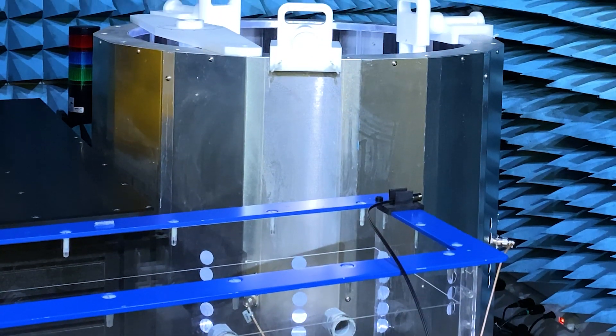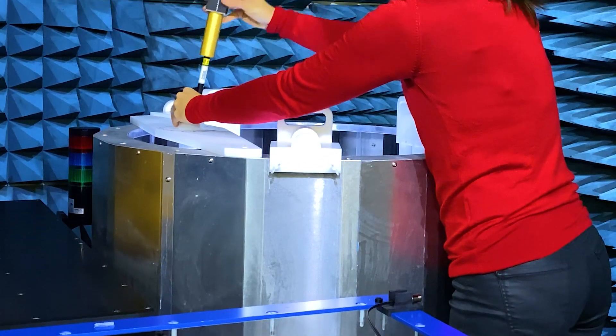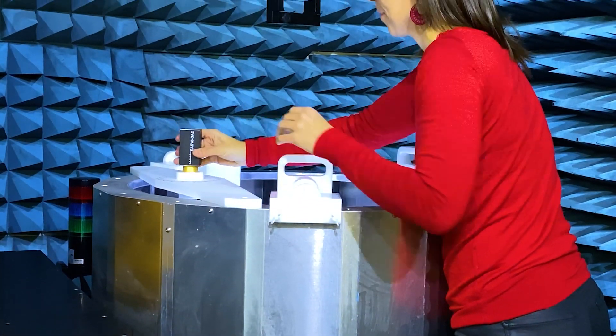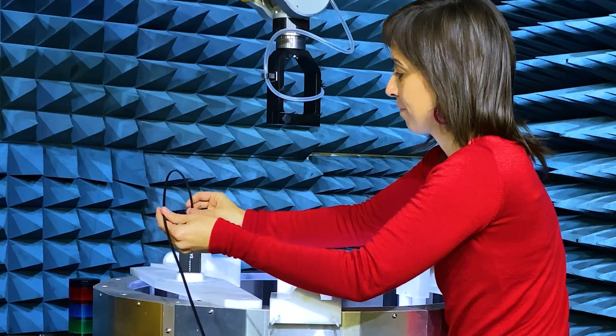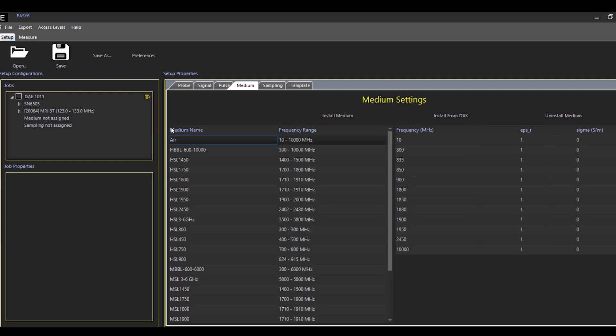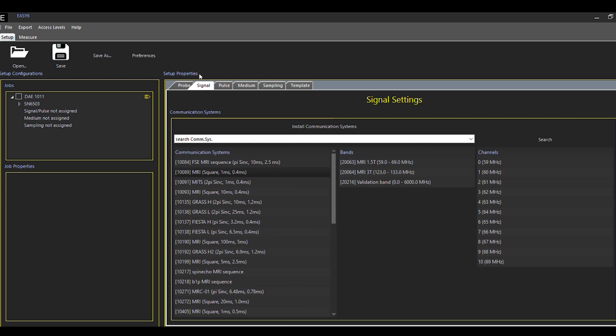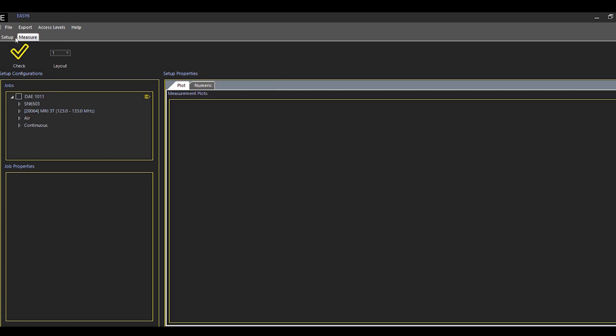In this example, we have installed the probe in the MIPS 1.5 system from ZMT-Zuri MedTech, and we are going to monitor the E-field. Let's configure our setup in the software. We can easily drag and drop the probe of our setup — in this case, the E-field probe. Then we install the medium, which is air. Then we define the communication system and create a new job. We change to the measure tab, check that the setup is right, and then click run.